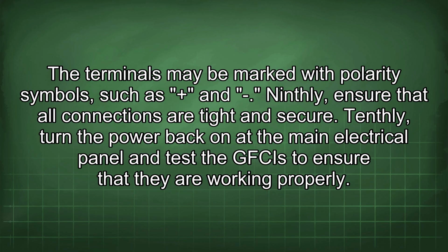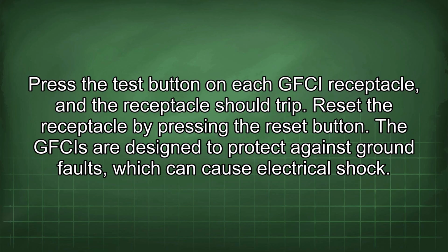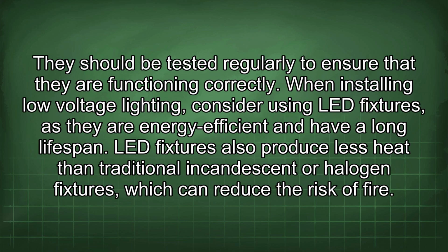Ninthly, ensure that all connections are tight and secure. Tenthly, turn the power back on at the main electrical panel and test the GFCIs to ensure that they are working properly. Press the test button on each GFCI receptacle and the receptacle should trip. Reset the receptacle by pressing the reset button. The GFCIs are designed to protect against ground faults, which can cause electrical shock. They should be tested regularly to ensure that they are functioning correctly.